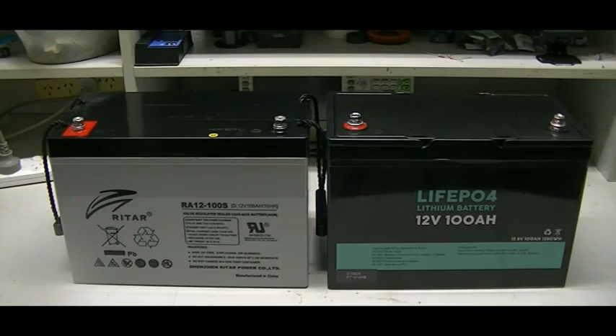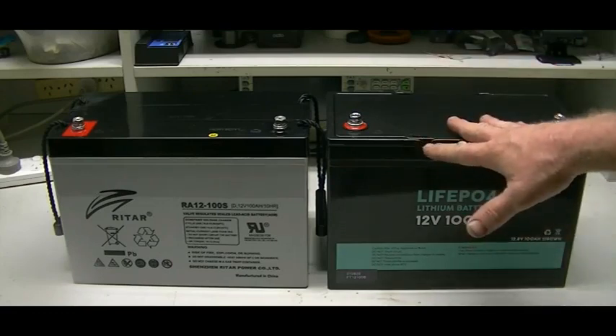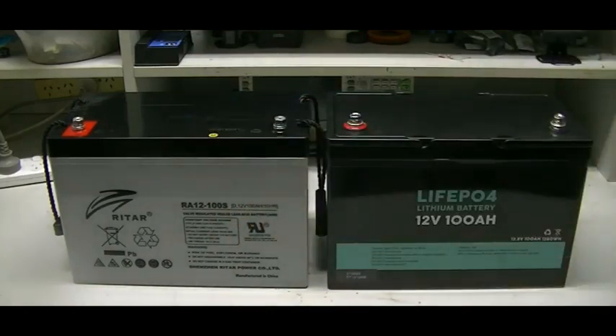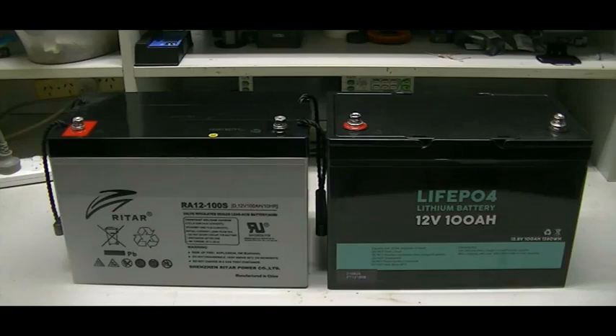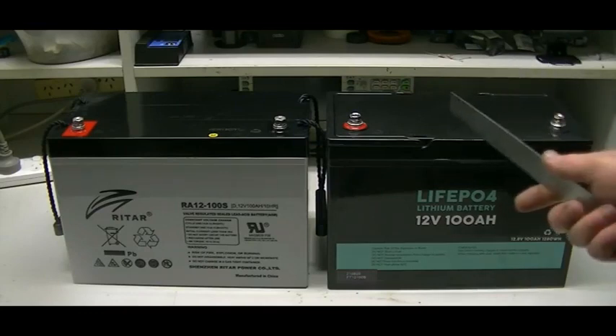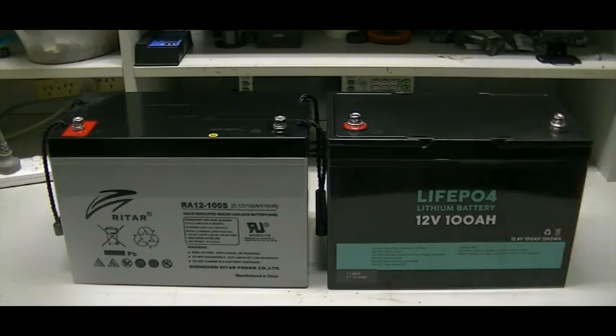Alright, the next test was a 15 amp drawdown test, carried out the same way - started on this battery, got 15 amps, did the test on this one, then swapped the load over to the other, done the same thing. For our AGM in the 15 amp drawdown test, I got 50.3 amp hours to 11.9 volts. For our lithium, I got 99.8 amp hours, so I nearly got the 100 amp hours, very close to it, at 15 amps draw. Not too bad at all.